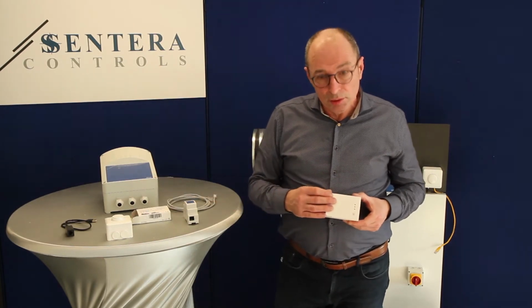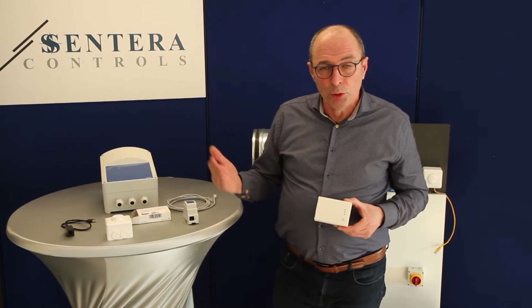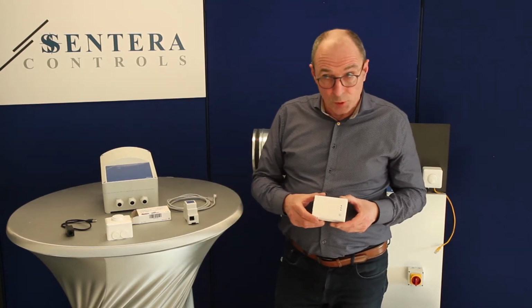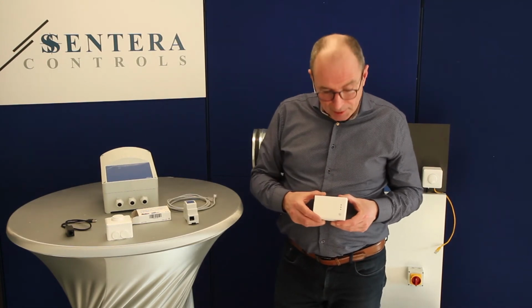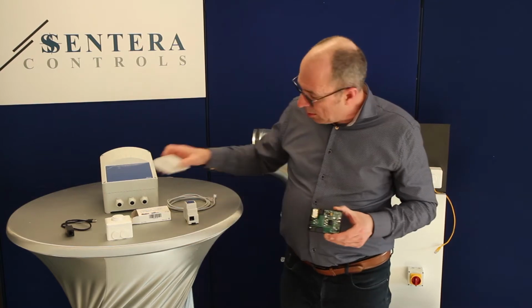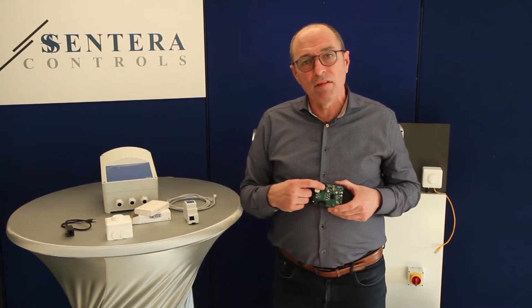Sentera sensors that can measure temperature, relative humidity, CO2, NO2, CO, TVOCs, that's indoor air quality, mostly exist in a version that has an RJ45 connector on board, power over Modbus connection.